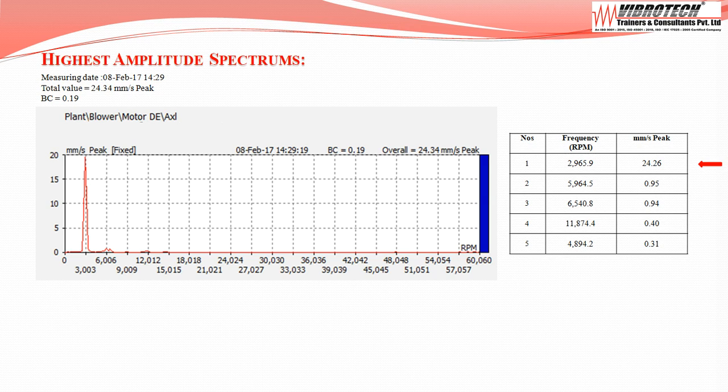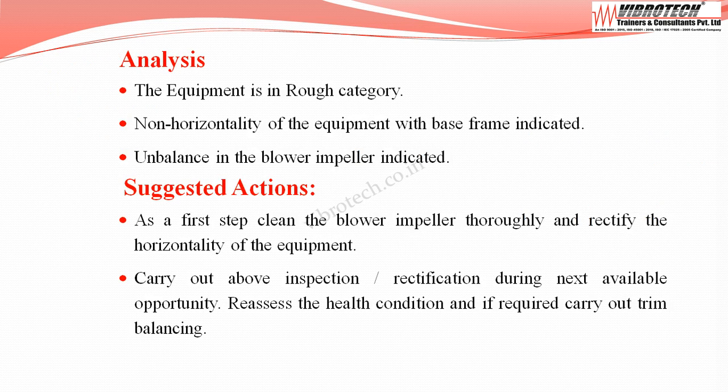Going through the spectrum, the dominant peak frequencies at the motor drive end are at 1× the running RPM. This indicates non-horizontality of the base frame and unbalance in the blower impeller. The equipment is confirmed to have both non-horizontality of the base frame and unbalance in the blower impeller.